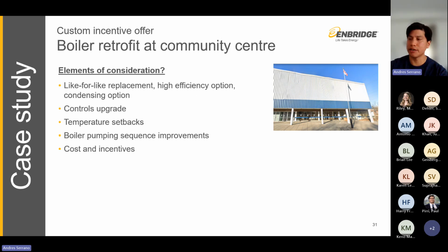So what are some of the elements of consideration? First, the customer could have gone for a like-for-like replacement, a high efficiency option, or a condensing option. The customer could have also looked at control upgrades, temperature setbacks, and boiler pumping sequence improvements. With all that said, any time you take on an additional upgrade, it does make the cost of the project slightly more expensive. So some things to consider are also the cost and the incentives that Enbridge Gas offers.